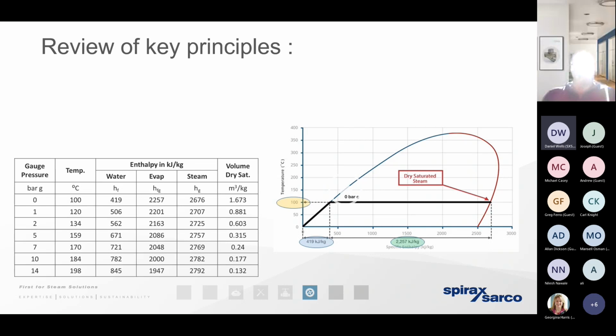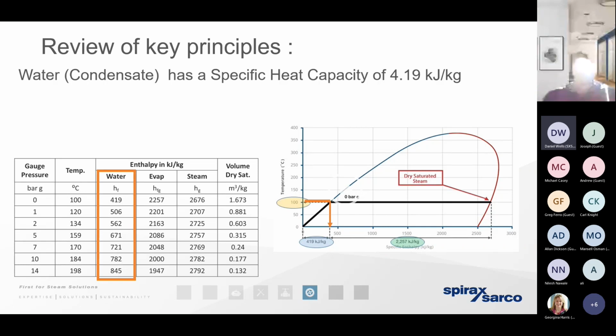In other words, if we know the pressure that the steam exists at, we know its temperature. If we want to hold the steam at a certain temperature, we can achieve that by manipulating the pressure. So we also know that water, the raw ingredient of a steam system, has a specific heat capacity of 4.19. The column highlighted in orange tells us the energy that needs to exist in the water before it will hit boiling point. And that's going to vary in accordance with the pressure that we're generating the steam at.